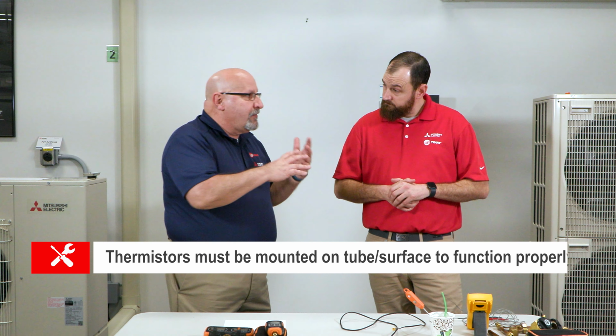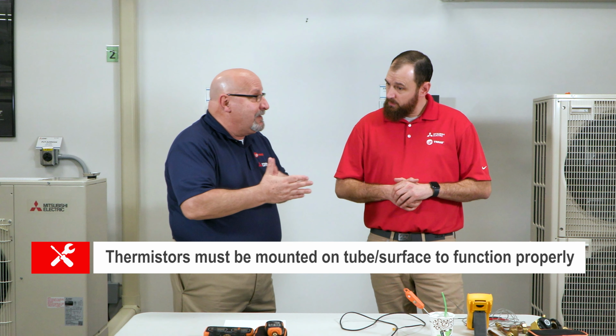So the typical thermistor failures that we may encounter, one is if the thermistor is out of range, if it's measuring too low or measuring too high. That's typically a shorted thermistor. Or an open thermistor, which you will see in an ohm meter as OL, because it doesn't have any resistance to measure there. So that's some of the typical failures. Of course, the thermistor has to be mounted on the tube or on the surface for it to work properly. Yes. So keep that in mind.